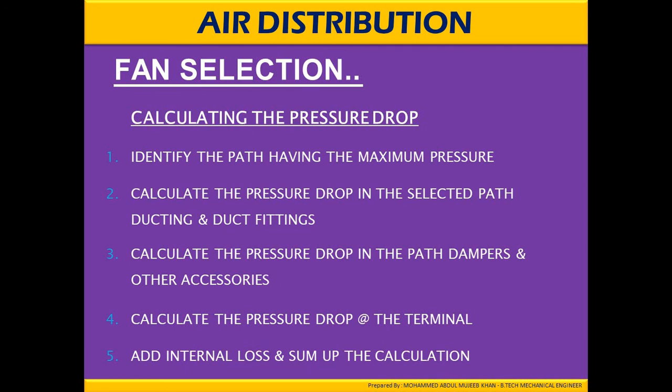Fan selection involves calculating the pressure drop: identify the path having the maximum pressure drop, calculate the pressure drop in the selected duct path including duct fittings, calculate the pressure drop across dampers and other accessories, and calculate the pressure drop at terminals including internal losses, then sum all the calculations.